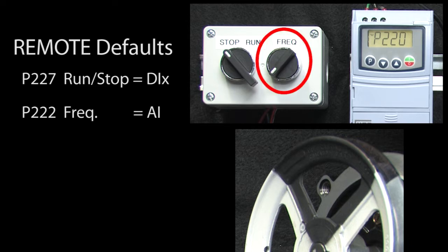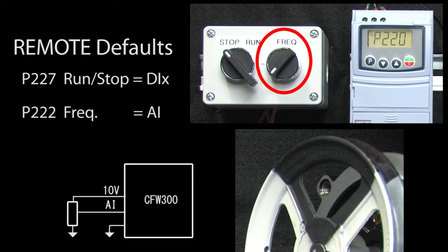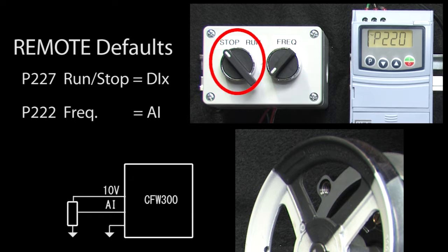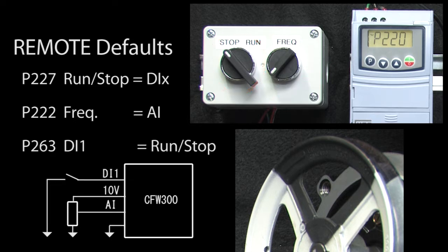I have this potentiometer wired to the drive's analog input and this switch connected to digital input 1, which if we look at parameter 263 we see it defaults to run-stop control – exactly what we want.